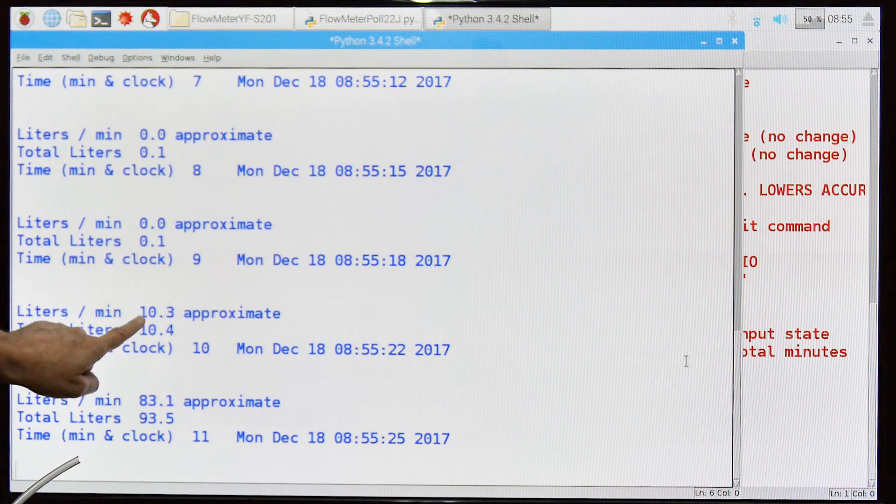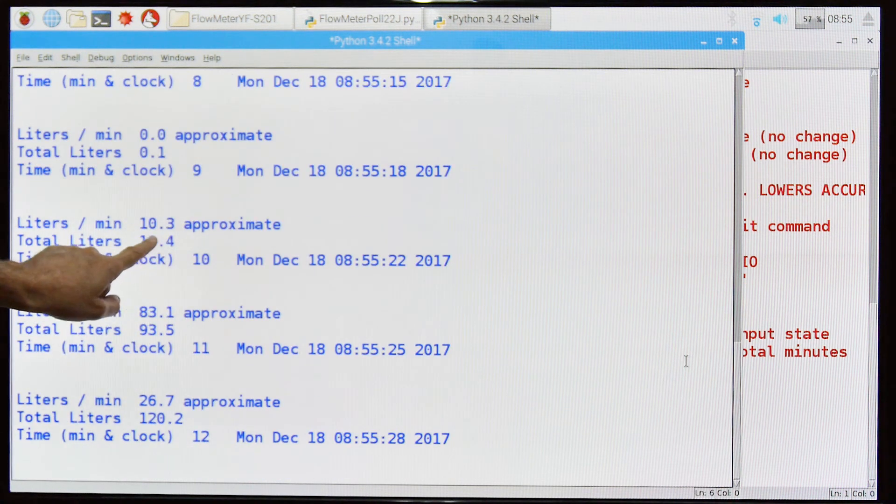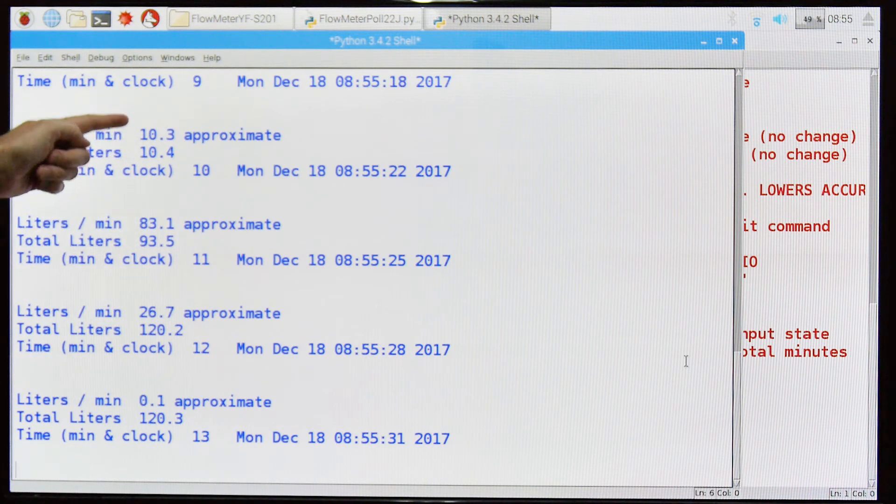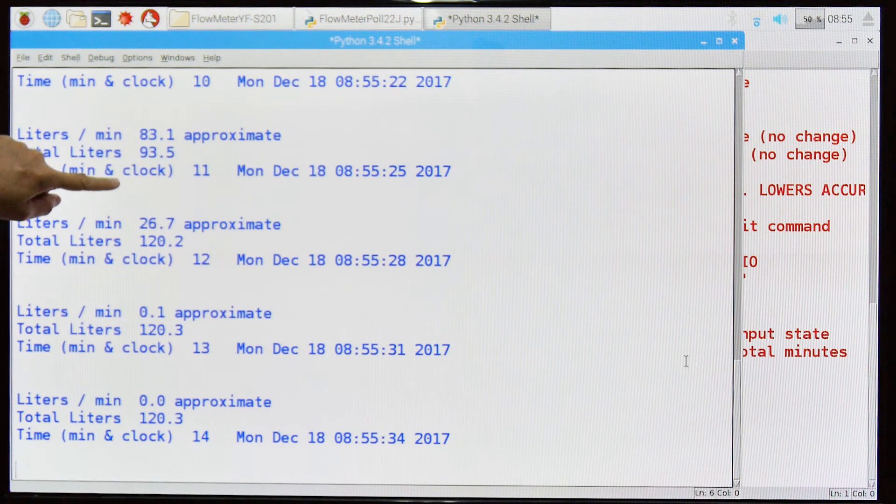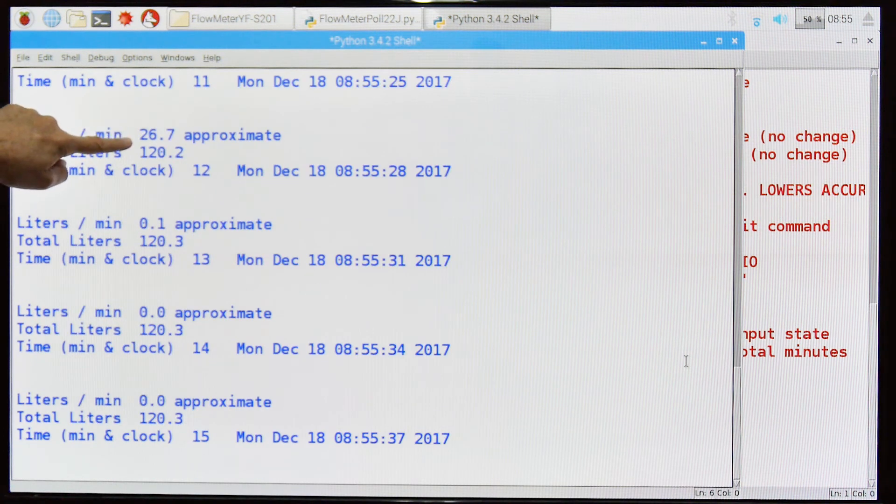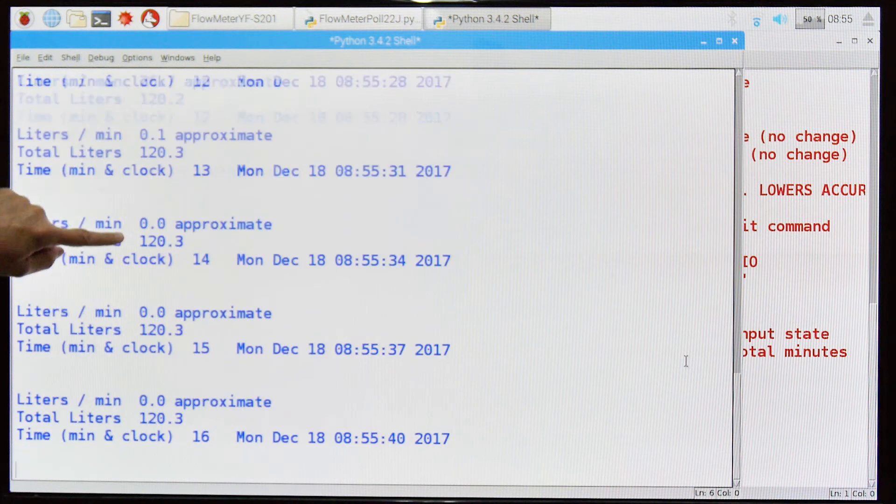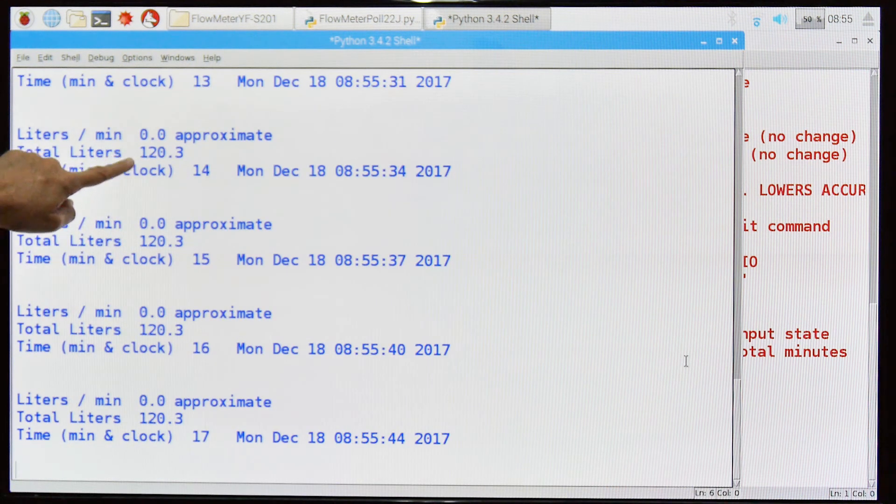So here you can see that the liters per minute rate, this is an approximate, this is an estimate, has jumped up and of course the total liters at first matches that. You can see that it's gone down, it went up and then it's going down now because I stopped blowing in it. You can see here that the impeller has stopped and that the total liters is not increasing, which is what it should be.